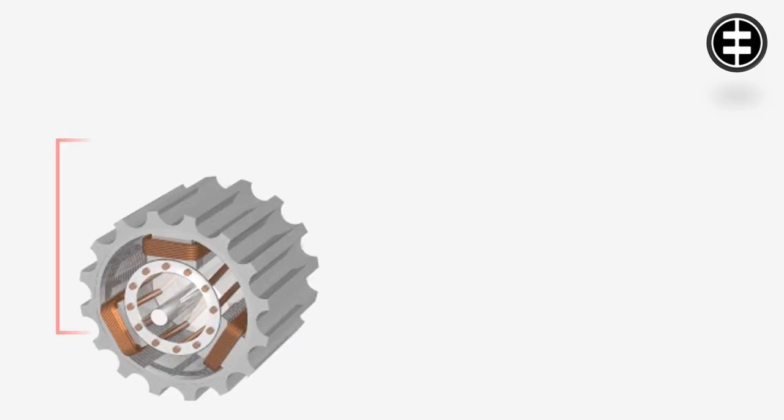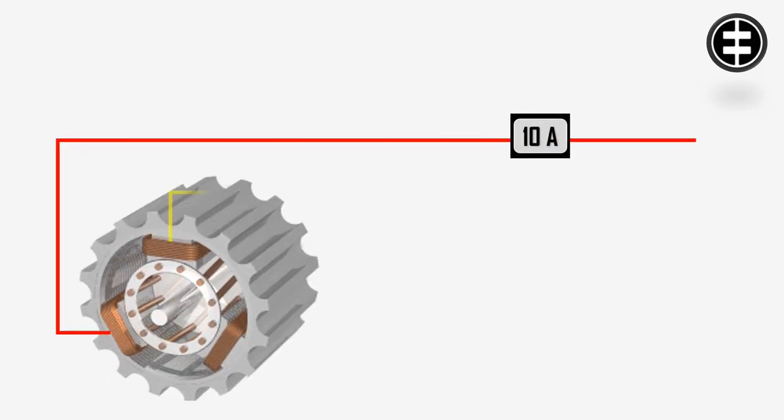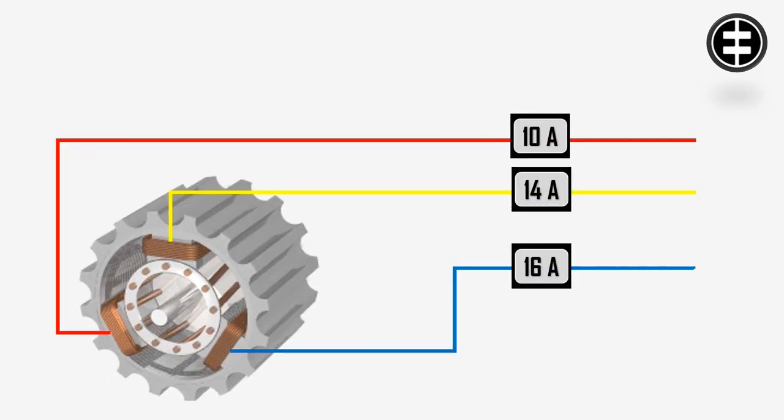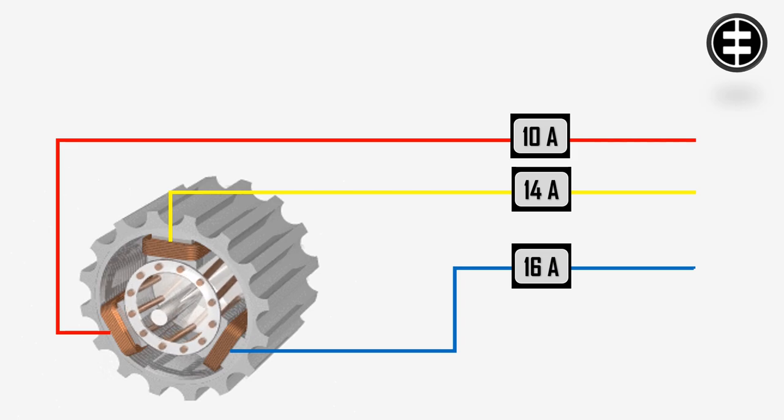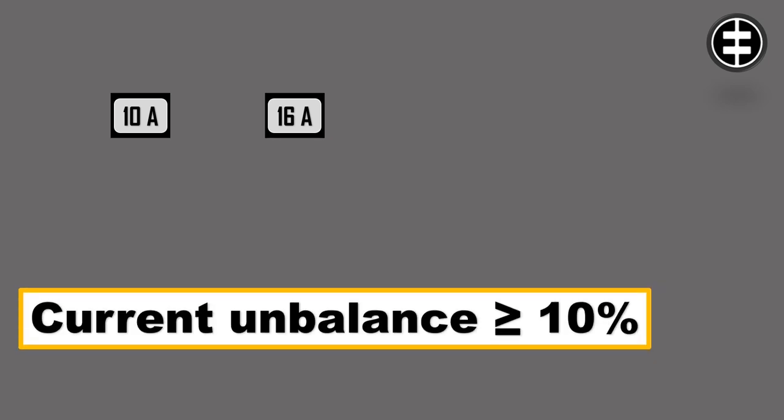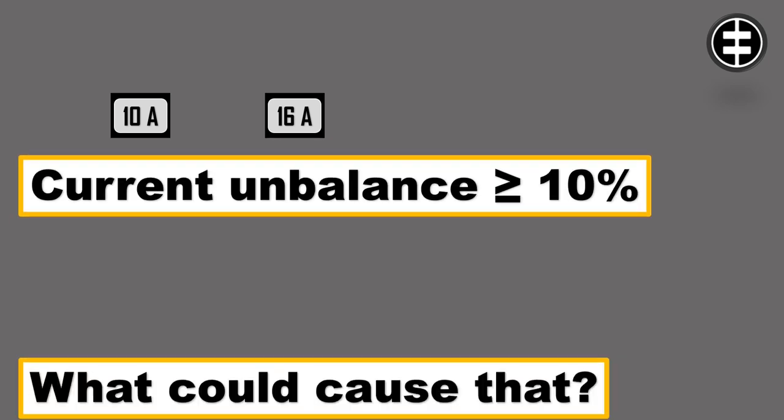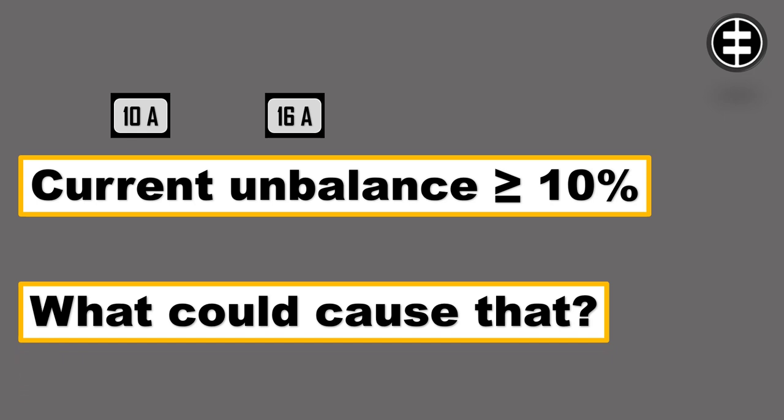What to do if you have a three-phase motor current unbalance. If the current unbalance exceeds 10%, you must take action to avoid motor failure and further asset damage. To solve the problem, we need to find the unbalance source and rectify it.